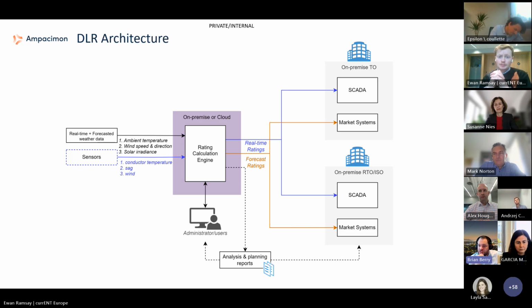The inputs into that system are, first of all, real-time and forecasted weather data. This comes from multiple suppliers out there, the weather company, Meteomatics, different weather providers. Fairly easy to switch that on and get that weather. For dynamic line rating, where you use the wind, you can bring in sensors from the lines and get additional capacity there. Those sensors typically measure the conductor temperature, sag, wind, etc., the local conditions around the line.